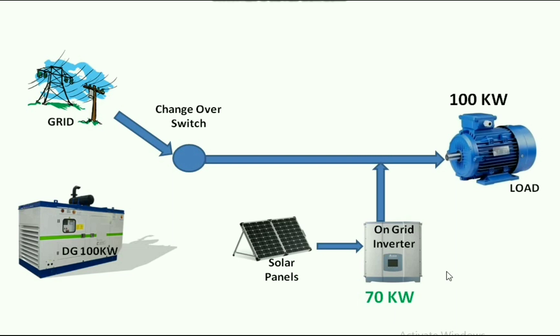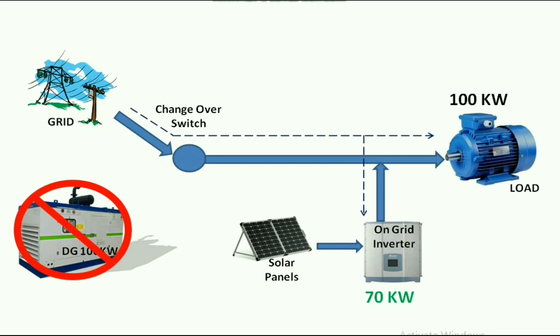When the load is getting supply from grid, the DG will be in off condition. When the grid is on, initially the power flows from grid to load and inverter, so the overall 100 kW load will be supplied by the grid. But when the on-grid inverter gets supply, it starts generating power from solar and begins sharing the load, supplying 70 kW from the solar inverter.